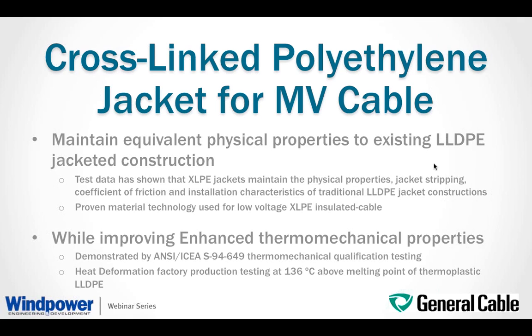So the XLPE jacket, again, will maintain equivalent physical properties to the existing LLDPE jacketed construction and improve the thermomechanical properties of the material. We have completed various testing, such as abuse resistance testing, including crush, impact, abrasion, and puncture resistance. We also completed jacket stripping, coefficient of friction, and flexure property testing, and compared the XLPE material performance to the existing LLDPE jacket material. The test data has shown that the XLPE jacket maintains these properties and insulation characteristics. On the other hand, you improve the thermomechanical property of the material by adding a thermoset material.